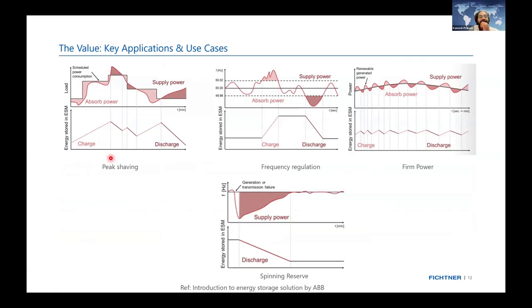This is a typical visual explanation for you, from ABB—peak shaving, how it looks. We will absorb, we will supply, absorb, supply. Whenever there is an excess, we absorb; whenever there is a shortage, we supply. So during charging time it's absorb, and discharge is supply. This is our SOC curve, and this is our load curve—the load supply curve. This is the frequency, where 49.98 is the lower threshold and 50.02 is the upper threshold.